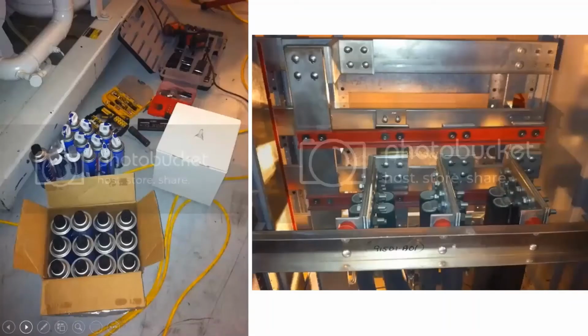Okay, cleaning. You get on a cleaning program, order the proper materials, the manufacturer will recommend them, but they have switchgear cleaning materials. You don't use Windex or anything like that. It's almost like an alcohol that evaporates and cleans the grease. It's designed and built for cleaning switchgear, and then you shine it all up.